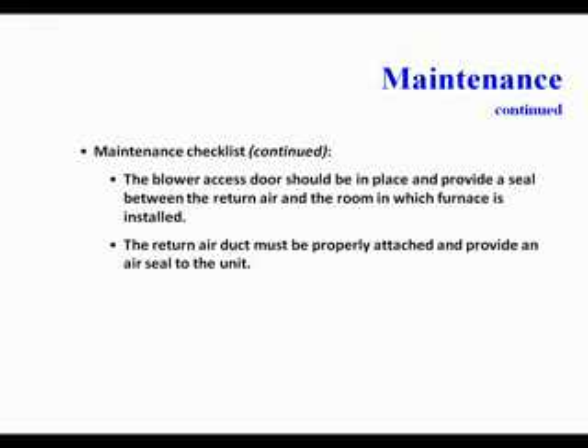Burners should be inspected for rust, dirt, and signs of wear. The vent pipe must be inspected for rust or sagging, dirt, signs of water, and damage or any disconnected joints. The unit should be inspected for rust, dirt, signs of water, and burned or damaged wires or components. The blower access door should be in place and provide a seal between the return air and the room in which the furnace is installed. The return air duct must be properly attached and provide an air seal to the unit.